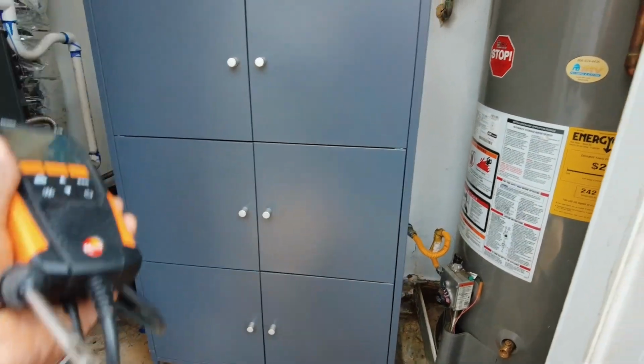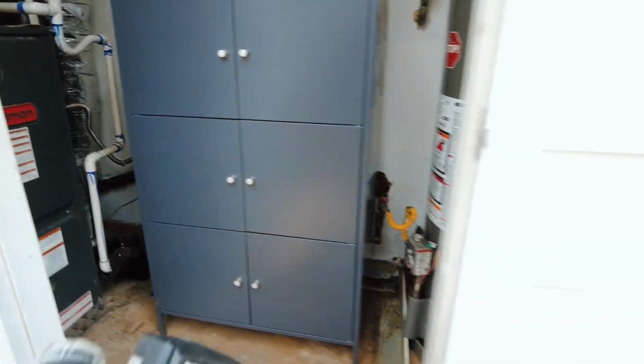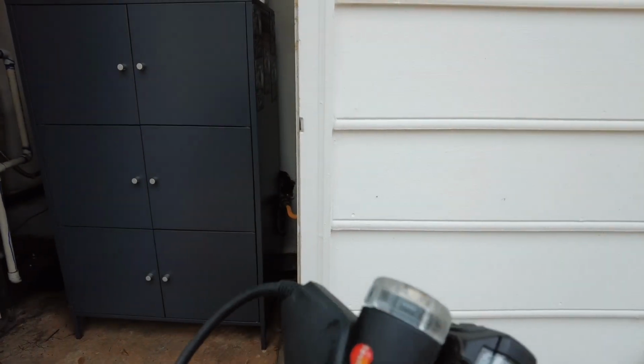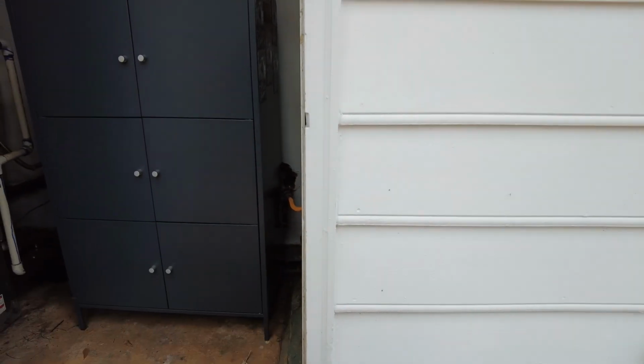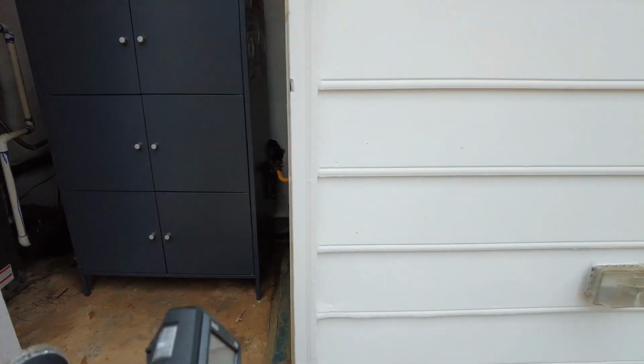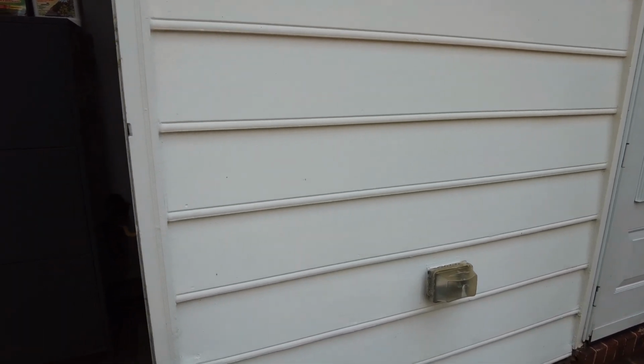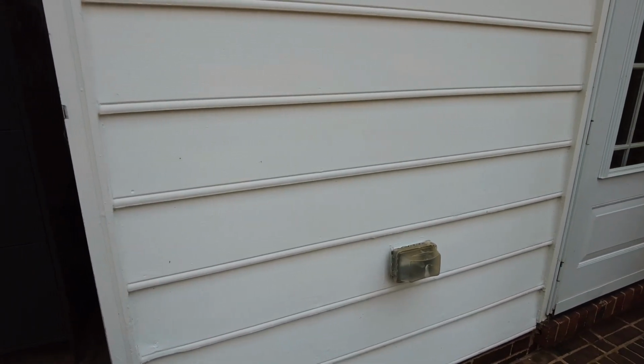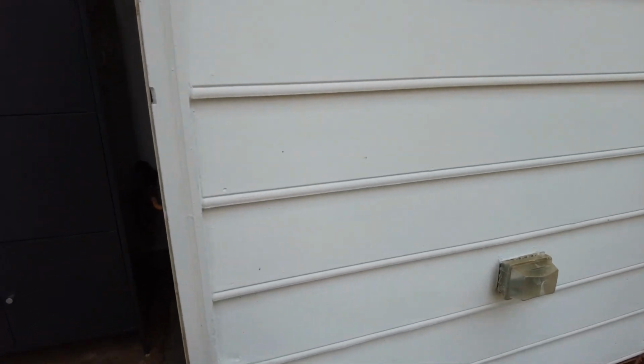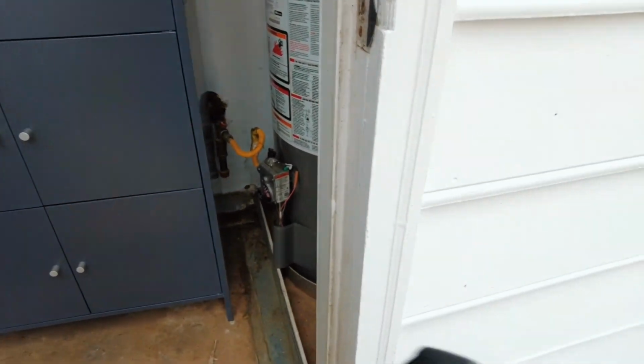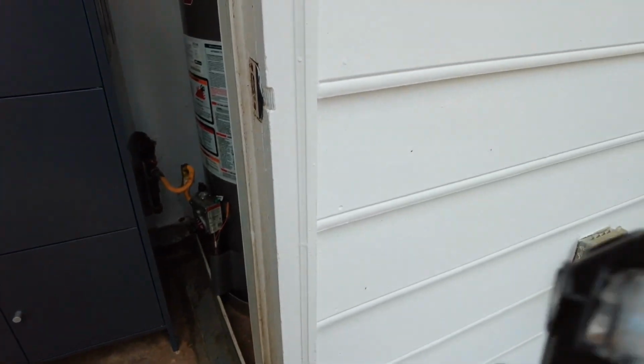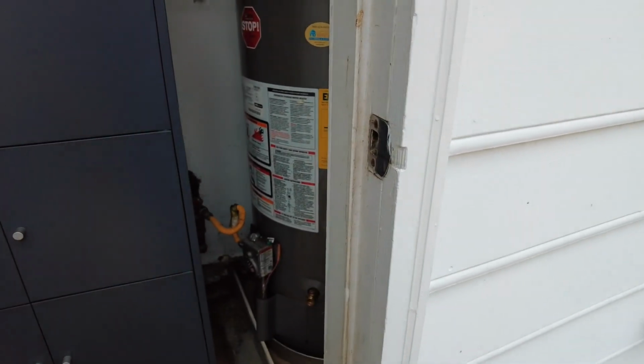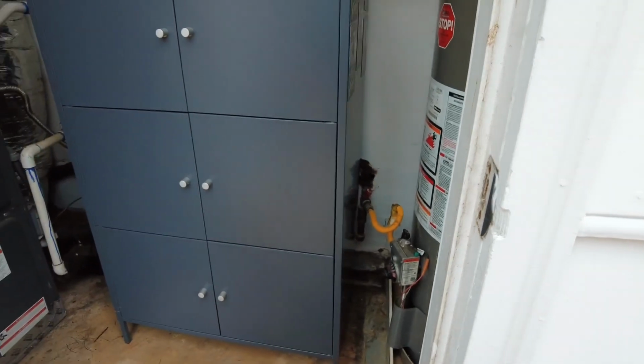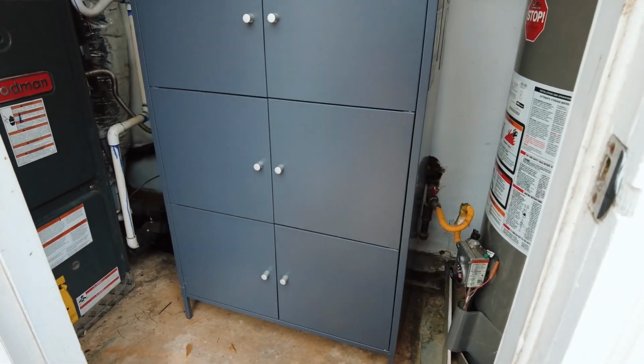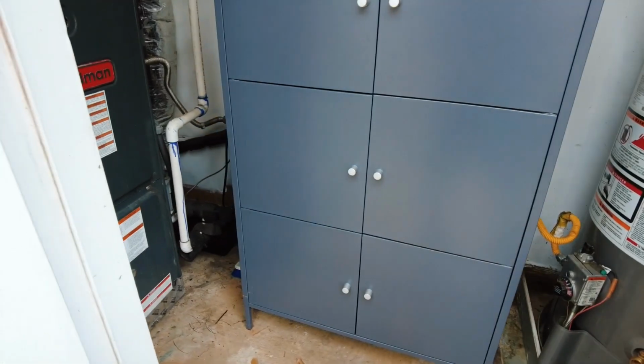Like I said, the only thing we probably want to address is that trap, because that trap is not properly oriented. It's probably been like that long enough that if it were going to cause any issues, it's probably already done it. But sometimes as sediment gets past it, it can make that gas valve fail prematurely by building up in the diaphragm. So address that, and the flexible pipe going outside. Those are the only two things I'd rush to get to. Other than that, looks good, man.